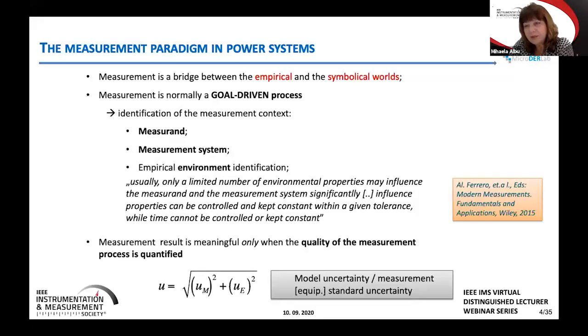And at this point, it's good also to recall what we also know, that a measurement result is meaningful only when the quality of the measurement process is quantified. And usually we quantify following the rules, for instance, of the expression of uncertainty in measurement, by this standard measurement uncertainty associated with a measurement chain or measurement equipment. Here it is depicted with UE, from the equipment.